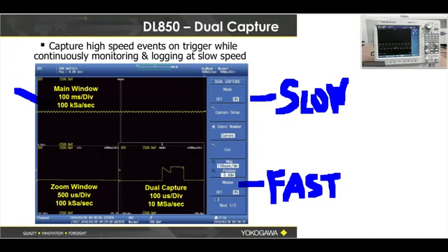So when you open up a dual capture waveform in XViewer, it will have all of these events in this list here. Right here I have a list. I could have 1,000 events or 5,000 events, each saved as a separate acquisition because each of those events met a criteria such as a surge. And that really is all dual capture is. It captures simultaneously at a slow speed, and then when it has events, it samples at a much higher rate.